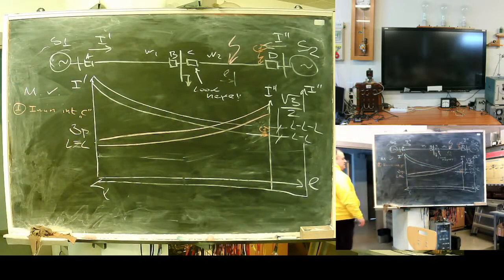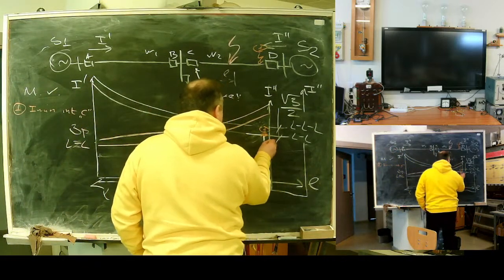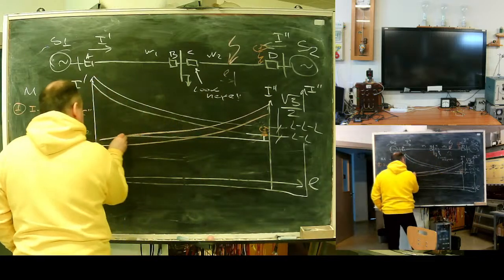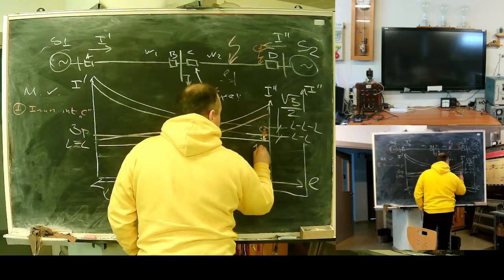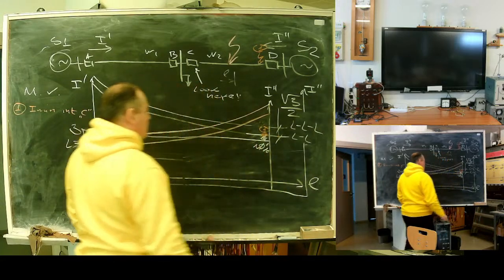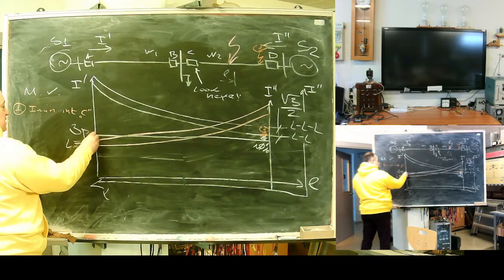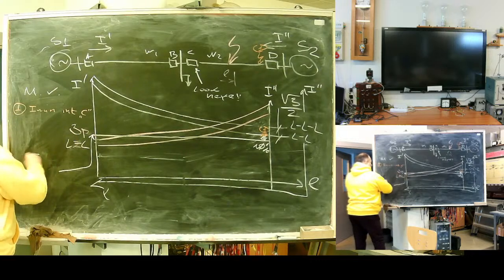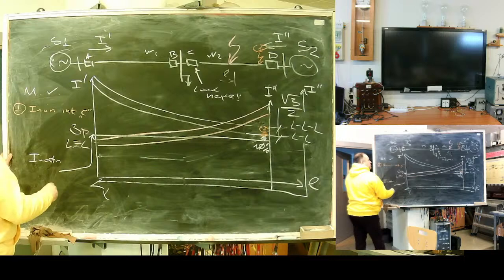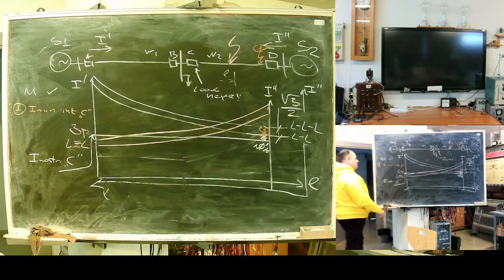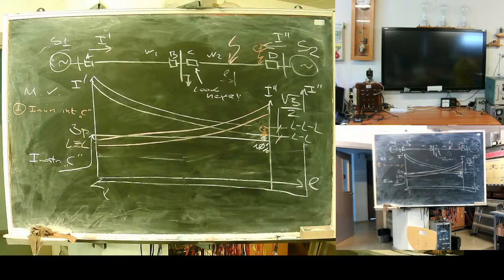So if my protection is sensitive, trip current for it should be at least 10% below 0.1. Yes? Approximately. Here, with a gap approximately 3%. This line is E, trip for protection C. Maybe it will be second zone, not important at this moment. What's important? Is it sensitive? Yes.